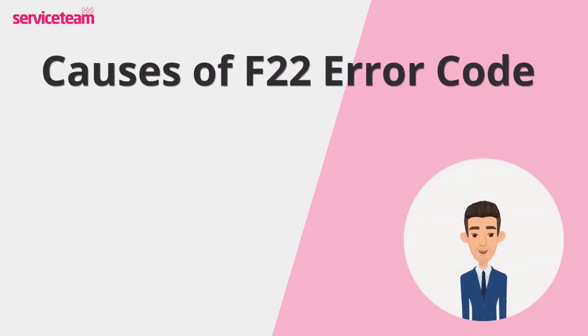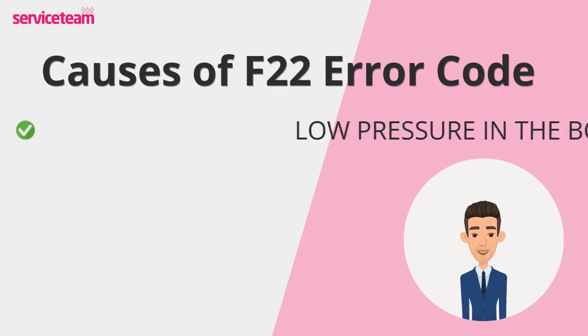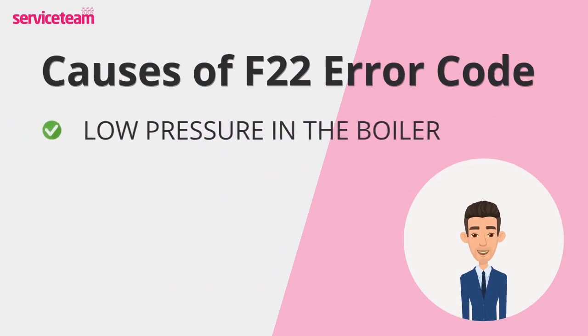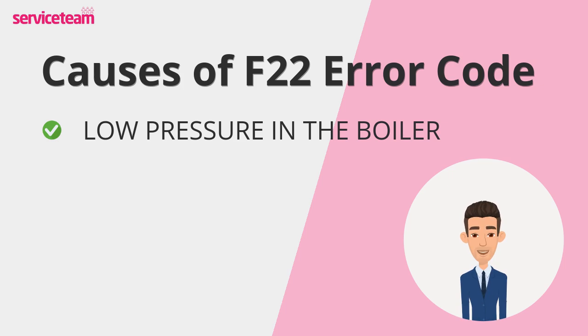Let's see what causes the F22 Glow-worm error code. One of the most common reasons for the F22 fault code in Glow-worm boilers is low water pressure. Boilers need consistent water pressure to circulate hot water effectively. When the pressure drops too low, the system can't function as it should.